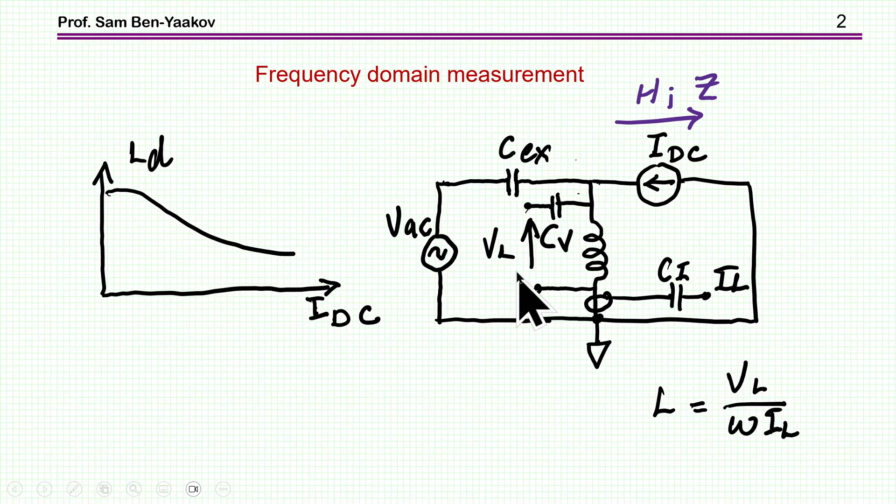The classical way of measuring the inductance would be to inject a DC current into the inductor, and then to have some AC excitation. Here I'm showing a voltage, this will be a small signal, a small amplitude AC signal at the given frequency. Then we measure the AC current through the inductor and the AC voltage across it, and by the impedance relationship we find the inductance.